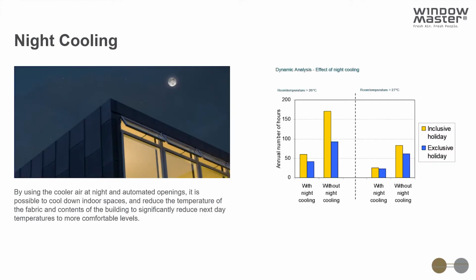Night cooling is a really important element of effective natural ventilation design. By using the cooler air at night, we're able to reduce not just the air temperature of the rooms and exhaust some of the excessive heat buildup during the summer daytime, but we're also able to reduce the temperature of the fabric of the building, any thermal mass that we have available, and that can include chairs, books, tables, anything that we can, just to reduce it to a good temperature and an optimum temperature, such that the next day some of the latent heat being generated by solar gain and the occupants and equipment can be absorbed by that fabric to help to keep the air temperatures much more comfortable and reduce peak temperatures.